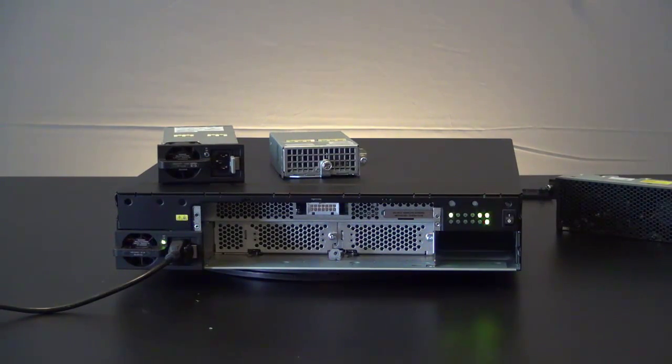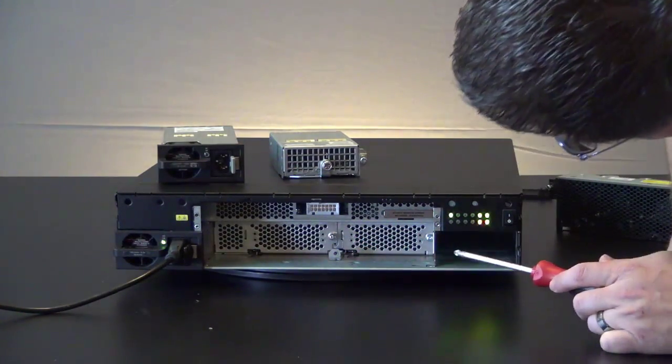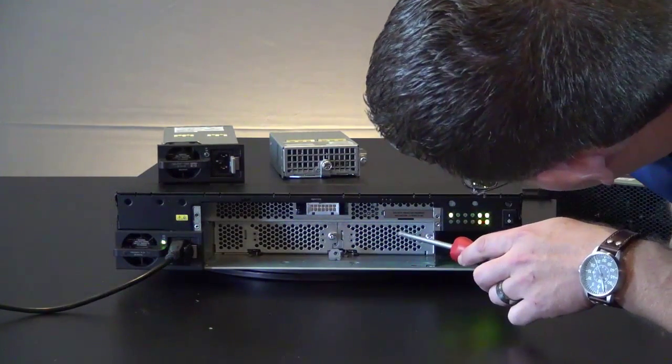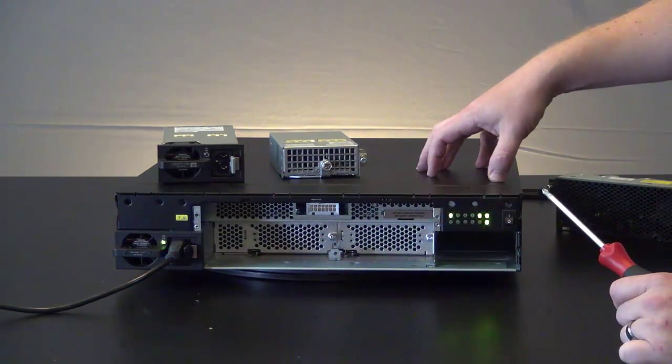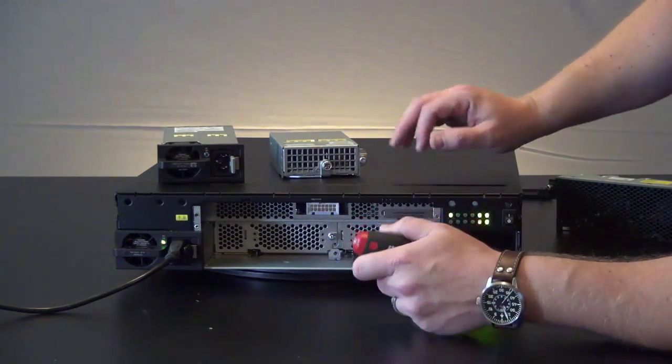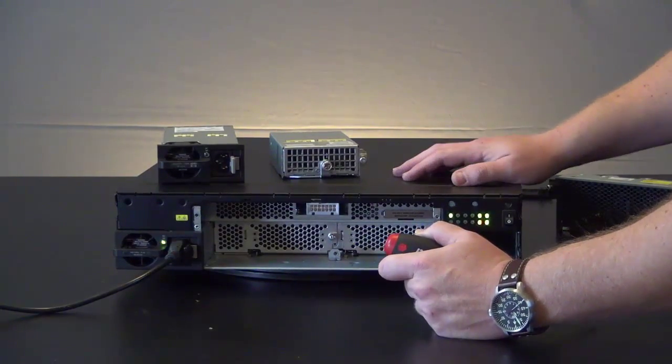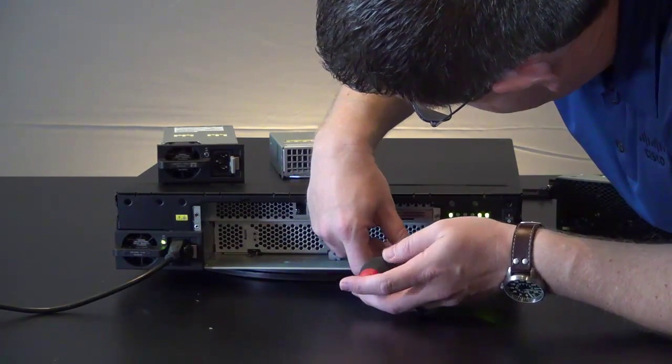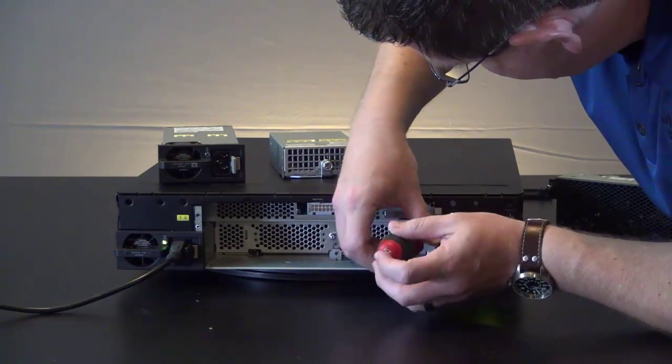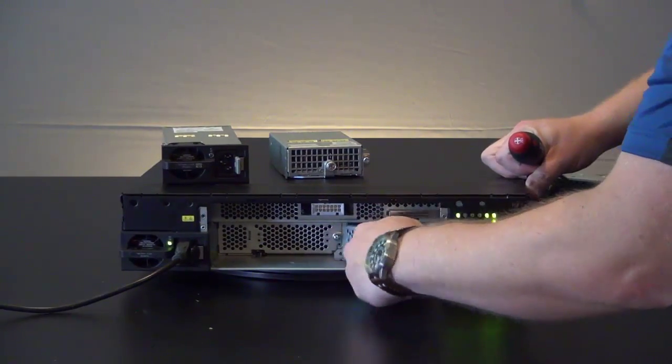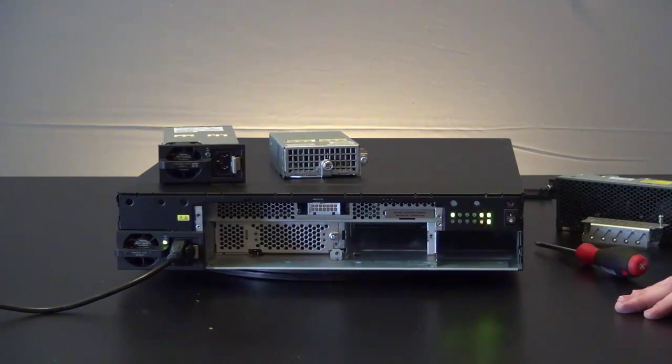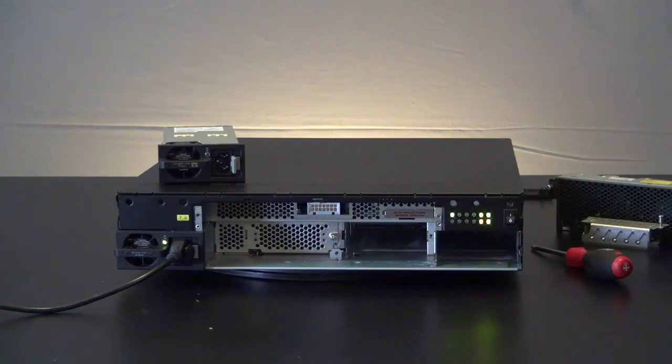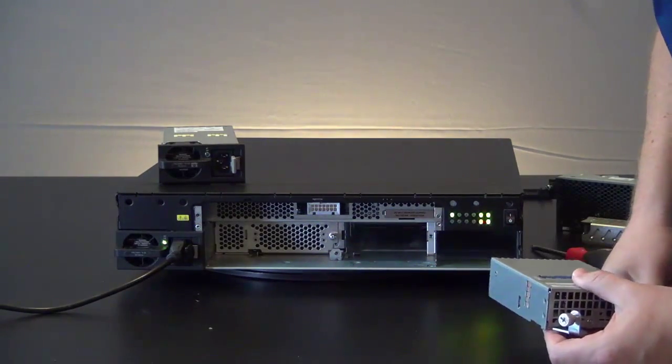You will see in here two PoE power supply bays. You'll also see up here a little metal cover that says do not remove during network operation. That's where you can find the compact flash, the actual boot flash of a 4451. And that's hidden back here because we are running a Linux operating system. It is a live functioning operating system. So, you don't want to upgrade that while the system is up in operation. We kind of hide it back here for you so that you can't just pop it out. So, I'm just going to remove the cover on one of these PoE converter bays. Again, I'll just loosen the screw. It's a captive screw, so it's not going anywhere. And then pull out this cover. Now, this is where you want to be really careful. There are some active voltages and active current inside of there. And you don't want to go sticking your screwdriver in there. You should not be able to stick your normal human-sized fingers in there. But you could certainly stick a tool in there.